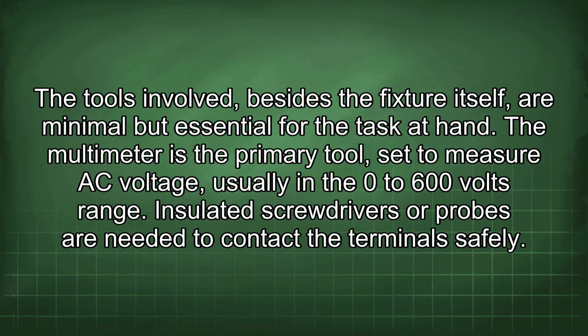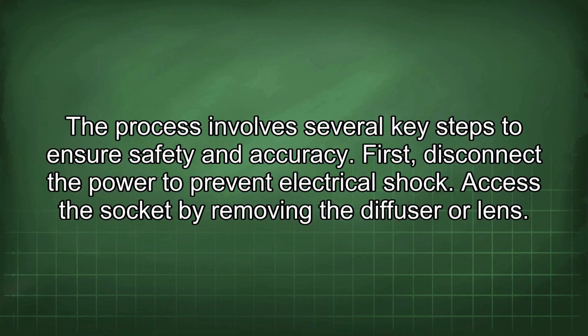The multimeter is the primary tool, set to measure AC voltage, usually in the 0 to 600 volts range. Insulated screwdrivers or probes are needed to contact the terminals safely. The process involves several key steps to ensure safety and accuracy. First, disconnect the power to prevent electrical shock. Access the socket by removing the diffuser or lens.